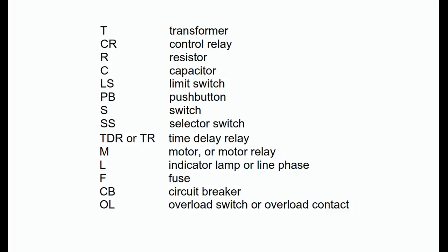It is generally a courtesy of the designer to state on the electrical drawing the last used reference designators. This is done so that anyone who is assigned the job of later modifying the machine will know where to pick up in the numbering scheme for any added components. For example, if the drawing stated last used reference designators: CR1-5, T2, F3, then in a modification which adds a control relay, the added relay would be assigned the next sequential reference designator, CR1-6. This eliminates the possibility of skipping a number or having duplicate numbers.